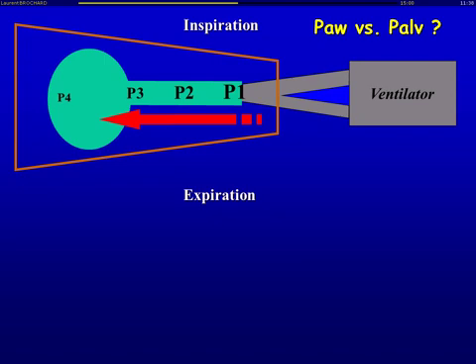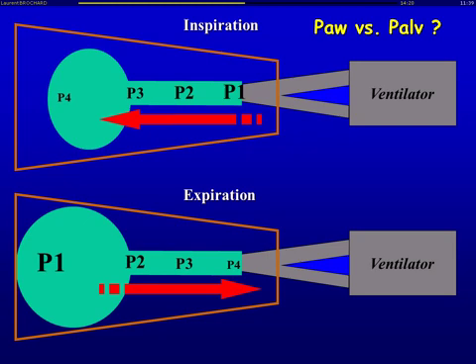Think again about resistance: during inspiration, because of resistance to flow, the pressure at the entry — the one you measure on the ventilator — is always higher than the pressure in the alveoli, and they become equal only at zero flow. During expiration, the gradient is in the opposite direction: the pressure you see on the ventilator is always lower than the alveolar pressure. At expiration they become similar only when there is no flow.